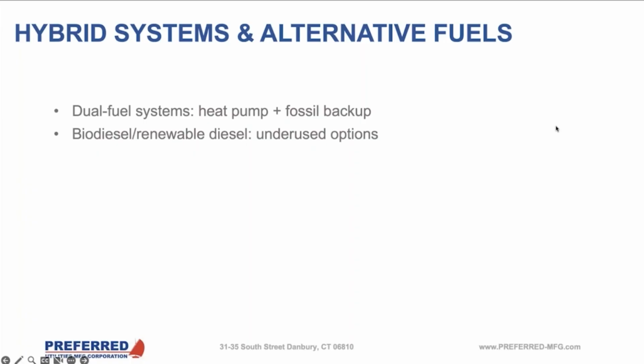Yeah, that's the main thing we see: a lot of these buildings want to go electrification and use air source heat pumps, but they don't realize that you need to do some extra work to get there. So if you just replace your air handling units and now you want to go electrification, and you sized those coils for the traditional boiler system you have there, say 200, 180 degrees, now you really have to replace them because you need to go lower.